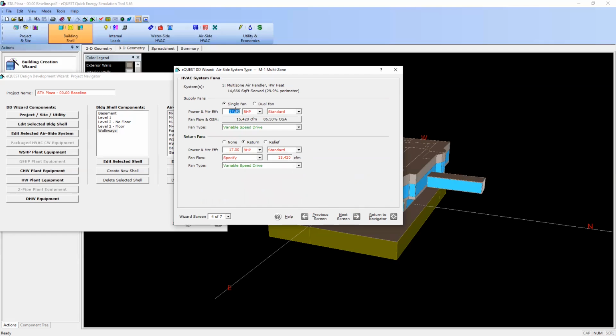Fan information. What's my brake horsepower? How much CFM am I doing? What's my fan type? In this case, they had variable speed drives on there, but we could have some inlet vanes or discharge dampers. And eQuest has some built-in energy curves. I don't know if that's the right term, but if I select discharge dampers or inlet guide vanes, eQuest has some built-in formulas to account for the energy use with those technologies, as opposed to a variable speed drive.